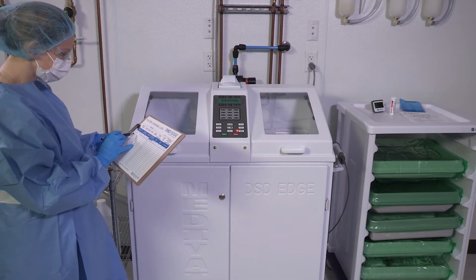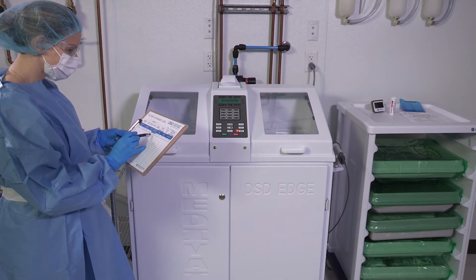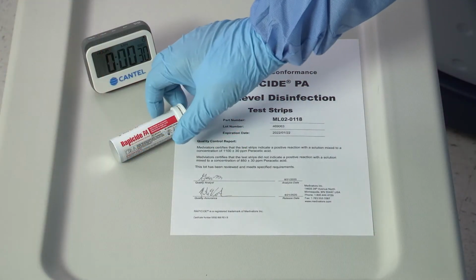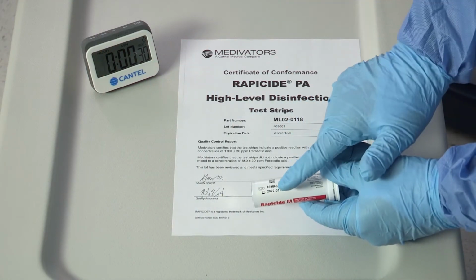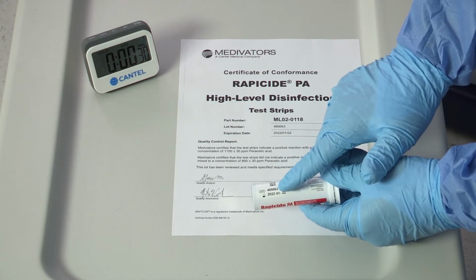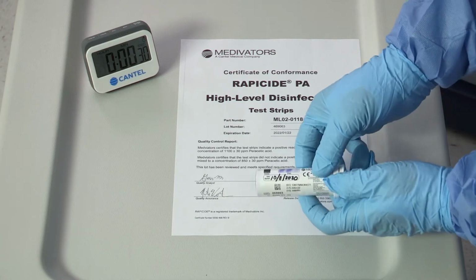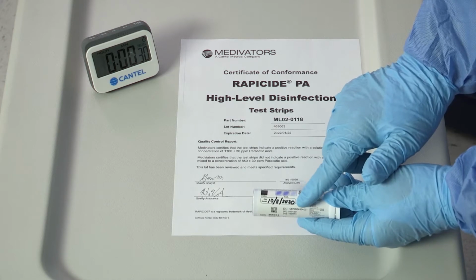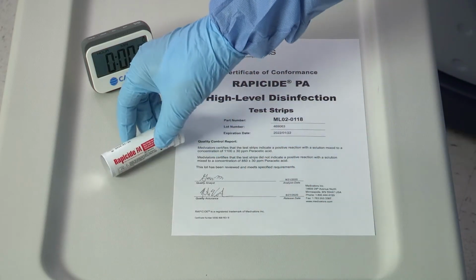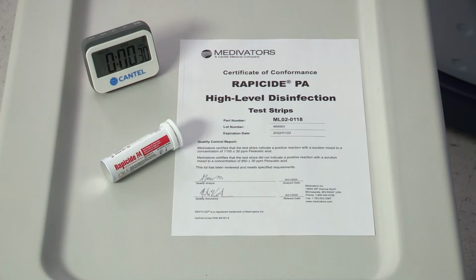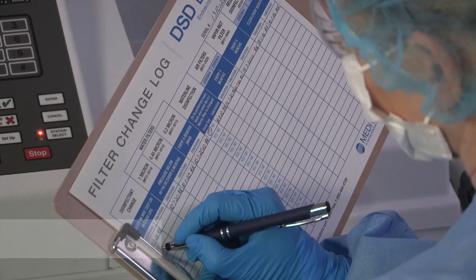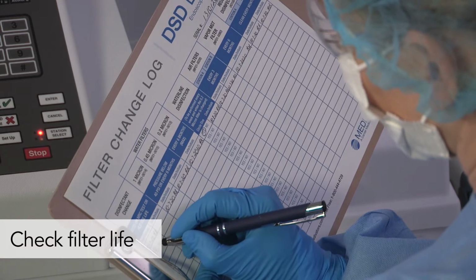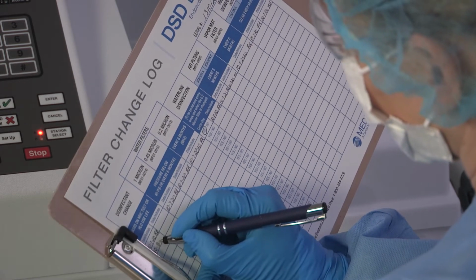The date opened should be recorded on the containers and in a log. Verify the Rapicide PA test strips are within their usable lifespan, which is 4 months after opening and prior to the expiration date on the container. The open date should be recorded on the bottle of test strips. You will also need to obtain a certificate of analysis for the test strips, which is discussed in the test strip quality control segment. Ensure the filters are within their use life. If not, change and document in the filter change log.